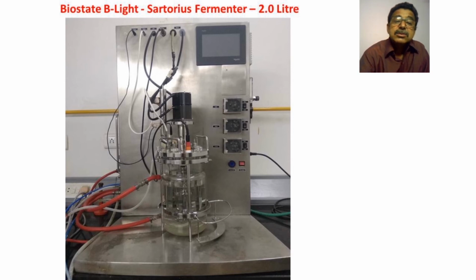But this machine is always advantageous compared to your New Brunswick, because here we have the facility of an air inlet, that is one thing, and second, an oxygen inlet. So we directly connect an oxygen cylinder with it, and it is PID controlled, where the dissolved oxygen probe senses the oxygen level inside. With growth of microorganisms, the oxygen level decreases, and when the level decreases, what happens? It has to be increased. So it is increased by increasing the agitation.